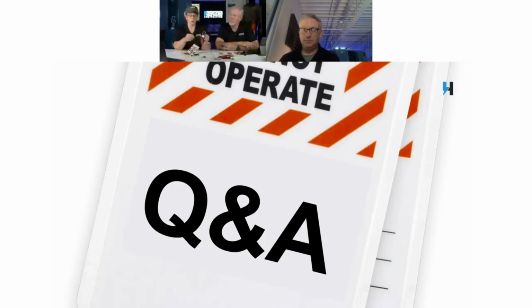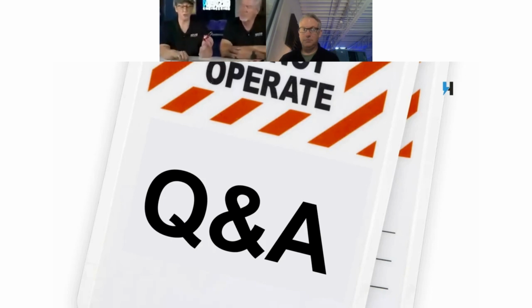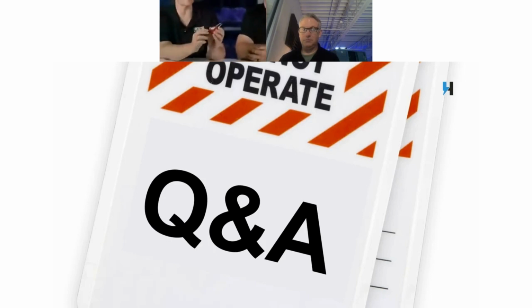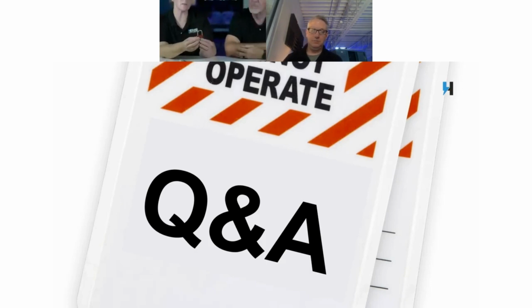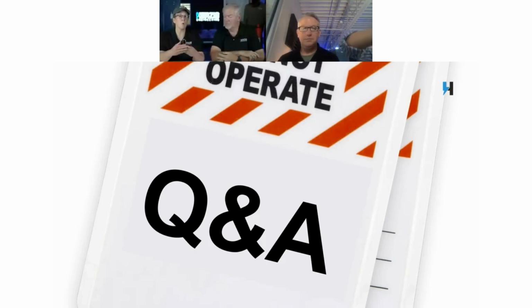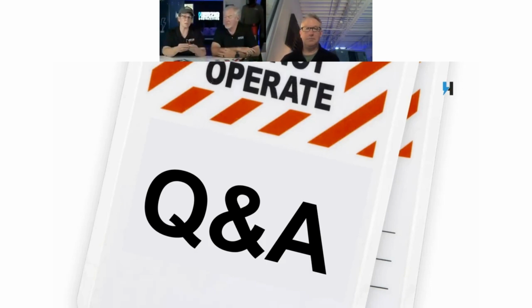As you can see here, we have danger, do not operate. This says danger, locked out, do not remove. And then on the back here, property of - you have room, although it's small, to put in a name and a date, and this could be replaced. That would be allowable. Locks or tags can be used separately or in conjunction - again, best practice is together, but they can be used separately.